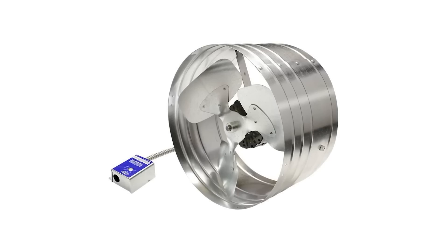The other thing that people try to do is increase the ventilation in the attic. When you increase the ventilation in the attic, you also generally are messing with the pressures between the attic and the occupied space. So things like powered vent fans or creating more cross flow through the attic — that can reduce condensation in the attic, but often it actually creates a pressure imbalance, driving more of that moist air into the space, which can then further increase the relative humidity and the total moisture content inside the house.